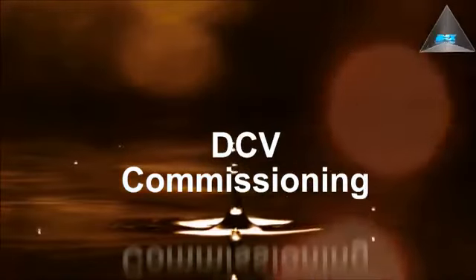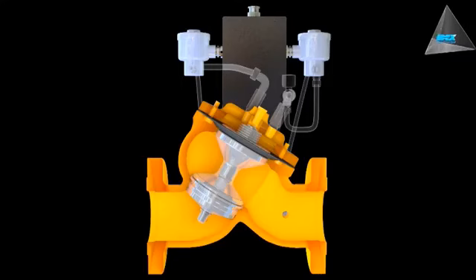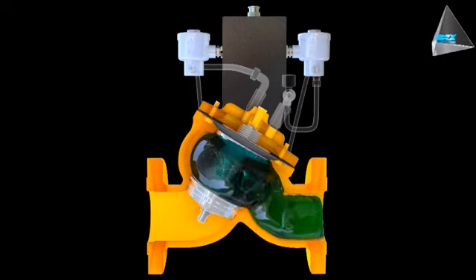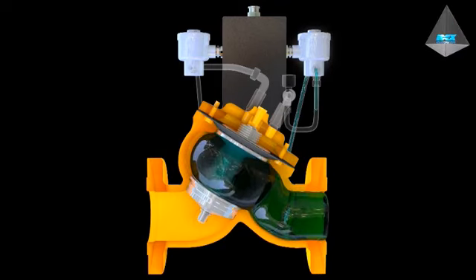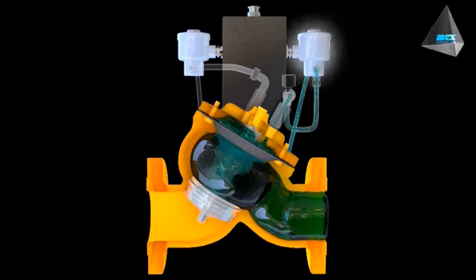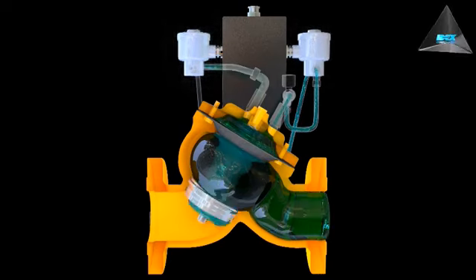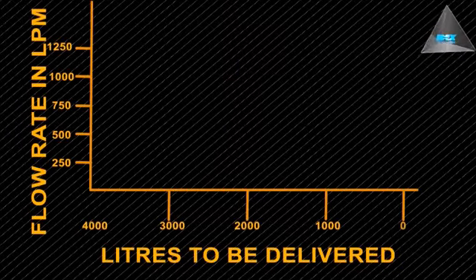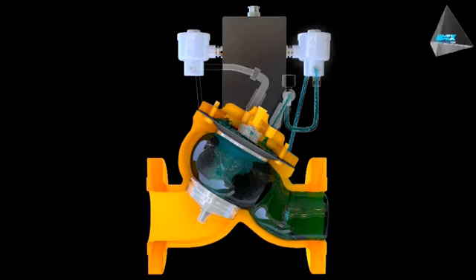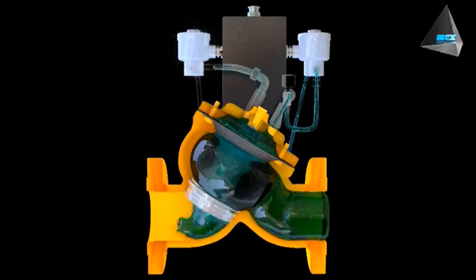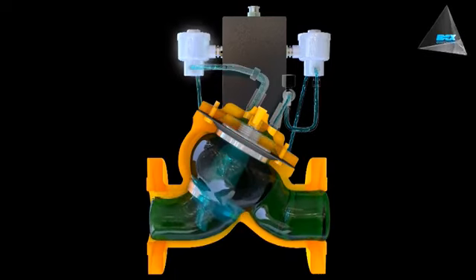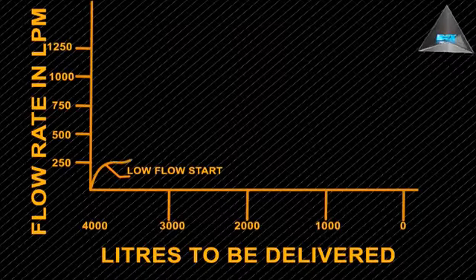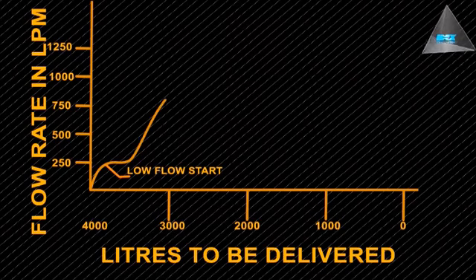DCV commissioning. Start the pump. The valve should remain fully closed. Bubble-tight shutoff is required. Energize NO solenoid. No flow. Energize NC momentarily and de-energize very quickly to lock the liquid in the cover. Observe low flow. This two-stage opening can also be made to operate in multi-stage. By repeating the steps, keep on energizing and de-energizing NO to maintain high flow at set level through batch controller.